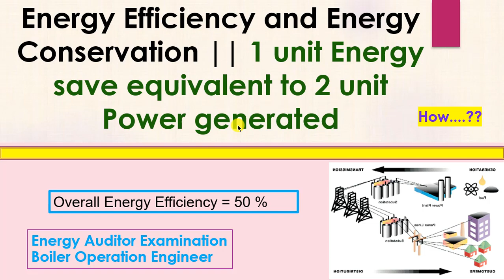It can be explained like this. Say in a factory far from the power plant there are several pieces of equipment. For our example, let us say one pump is consuming 300 kilowatt hour energy per hour. Suppose after overhauling or taking an energy saving measure, it is consuming 280 kilowatt hour. That means the energy saved at the user end is 300 minus 280, equal to 20 kilowatt hour. So 2 into 20 kilowatt hour, equal to 40 kilowatt hour of energy, does not need to be generated at the power plant end. That means 1 unit energy saving is equivalent to 2 units power generated.